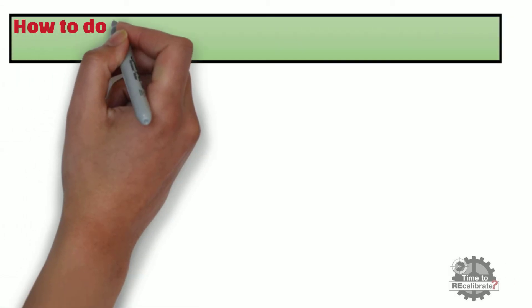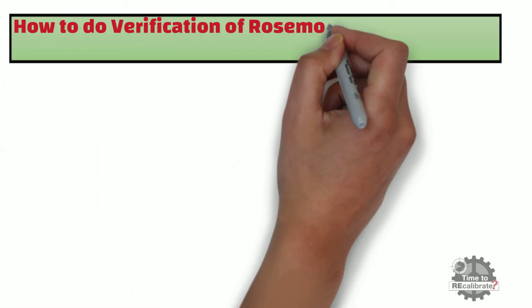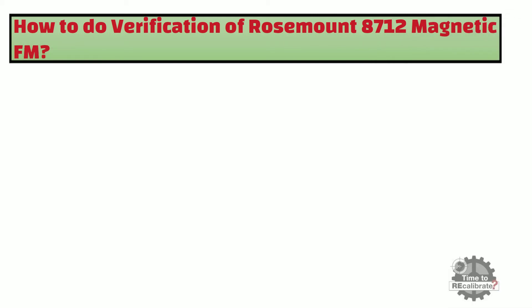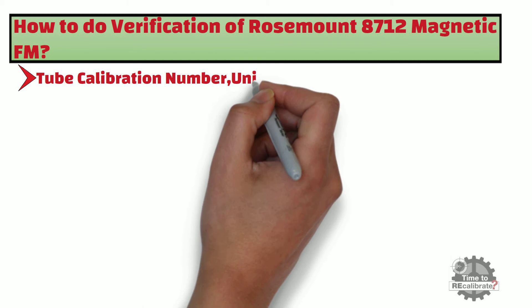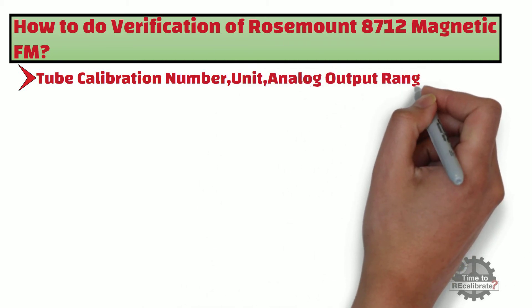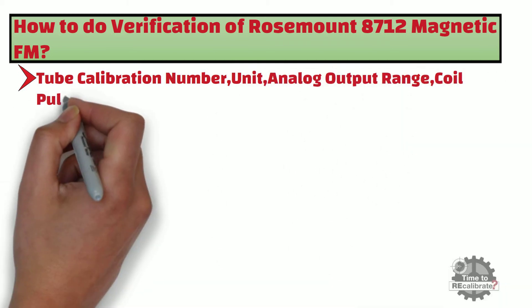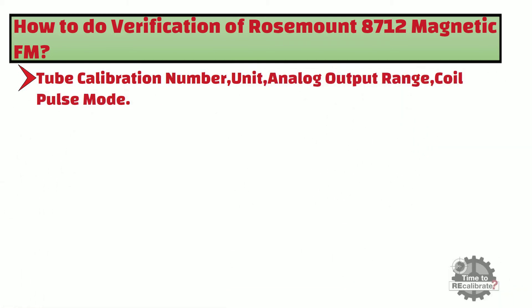Let's learn how to do verification of the Rosemount 8712 magnetic flowmeter. Step 1: Note down all existing parameters of the flowmeter, such as flow tube calibration number, unit, analog output range, and coil pulse mode. We are going to change all these parameters, so it is important to note them down before making any changes to the transmitter.